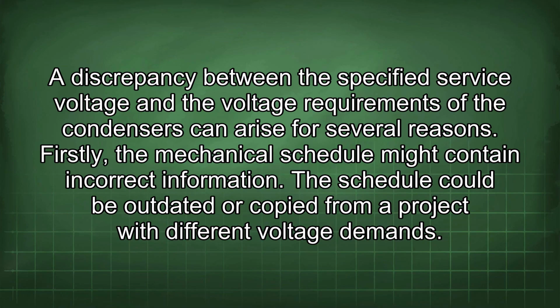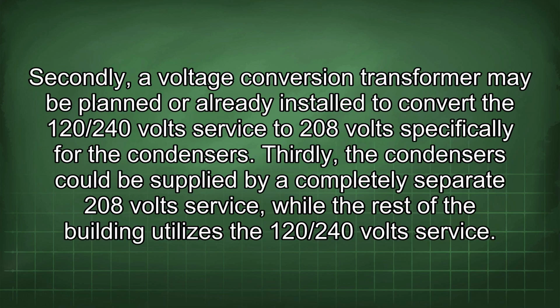A discrepancy between the specified service voltage and the voltage requirements of the condensers can arise for several reasons. Firstly, the mechanical schedule might contain incorrect information. The schedule could be outdated or copied from a project with different voltage demands. Secondly, a voltage conversion transformer may be planned or already installed to convert the 120/240 volt service to 208 volts specifically for the condensers.